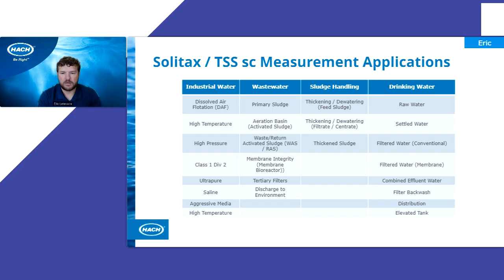As Steve mentioned, there are a number of different applications where we would want to monitor turbidity or TSS. In industrial water, we'll mention a DAF in the next few slides. Maybe there's a high temperature or high pressure application. If it's a refinery or a chemical plant, there might be a Class 1 Div 2 requirement, a hazardous environment we need to be aware of. So there are a number of applications where we would want to use a turbidimeter or TSS probe to measure in real time or in line.